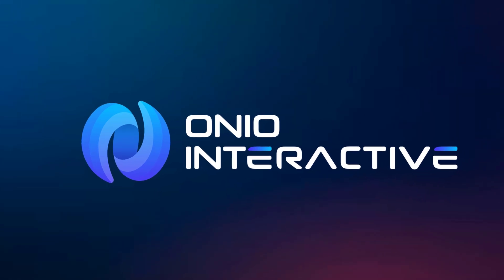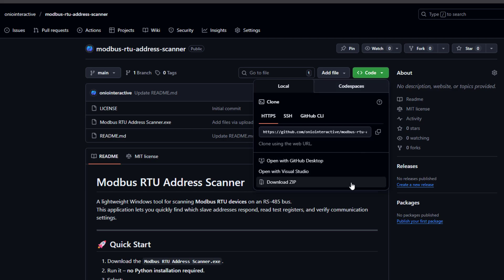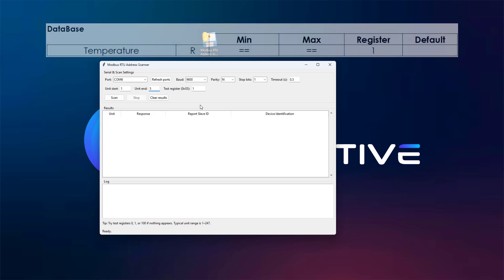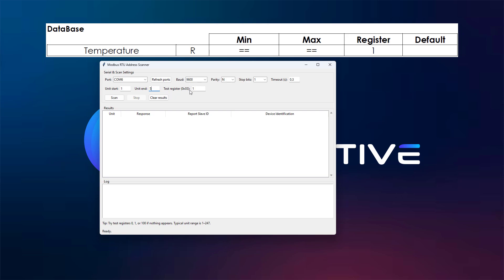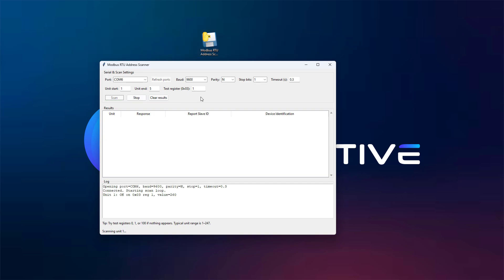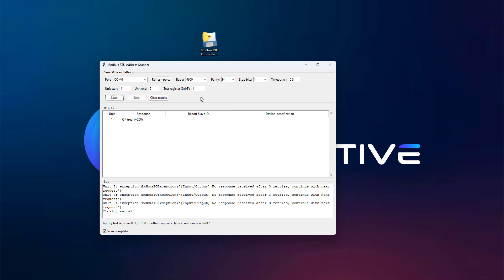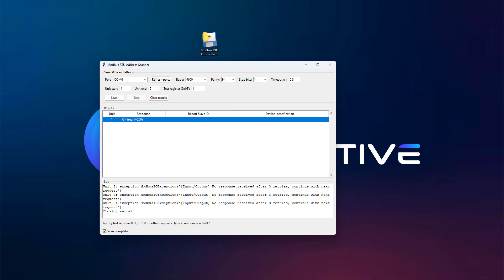To do that, we'll use the Modbus RTU address scanner, which you can download from the GitHub repository linked in the description below. After downloading, simply run the executable file to open the program. Inside the scanner, configure the serial parameters according to the device's documentation and be sure to select the correct COM port. In our example, let's assume the slave address is somewhere between 1 and 5, so we'll set the unit start and unit end fields accordingly. For the target register, we'll enter 1, since we know from the documentation that this register represents the ambient temperature. We can now start the scan. After a few seconds, we can see that the program has detected our device at unit 1.